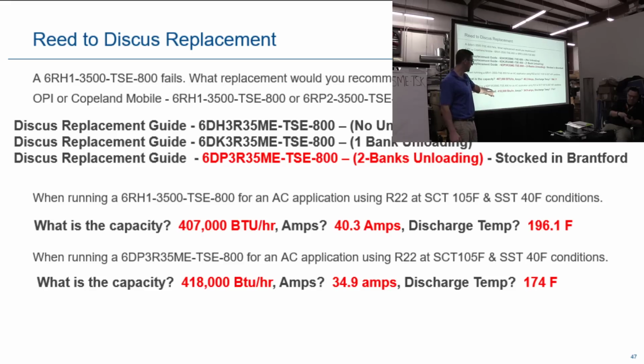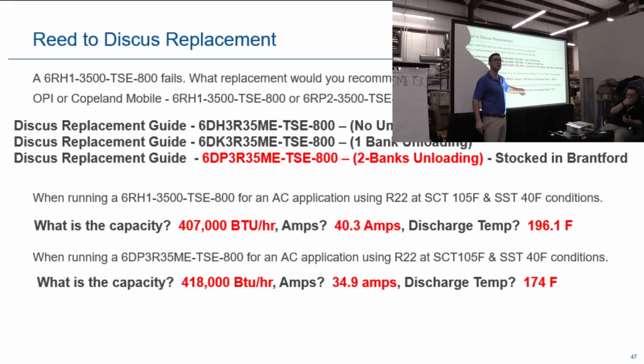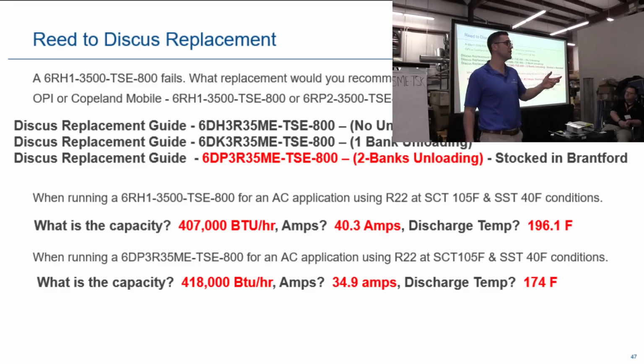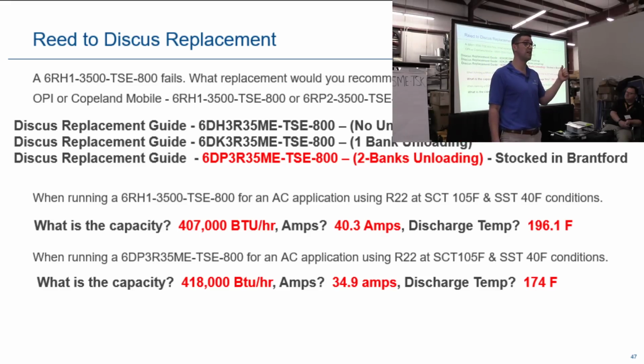Now look at the capacity, 418,000 BTUs. So we got more capacity. Look at the amp draw now. So is there an efficiency gain there for your customer? Yeah, for sure. Not every reed compressor to a Discus is going to be a perfect swap one for one, right? You might have to change service valves on certain of them.